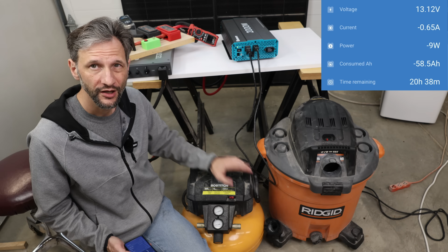Now I have a pancake air compressor and a shop vac. I'm going to check the inrush current when I turn this on. Should be a big surge. 180 amps, that's a pretty big surge.